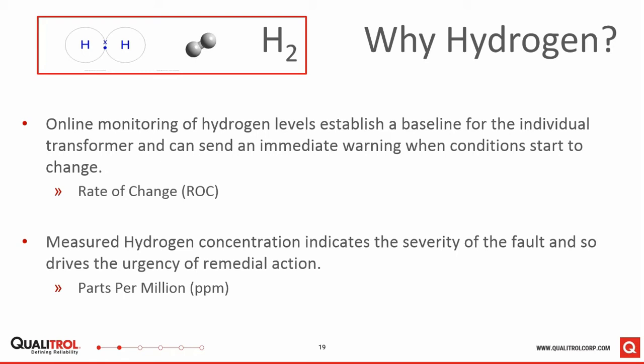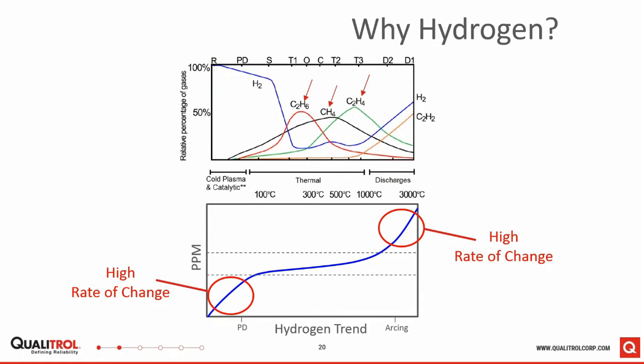Looking at the concentration itself, the ppm concentration provides some quantification of the severity of the fault, for the simple reason that the more gas present is likely to equal a more significant fault. So concentration equates to seriousness of the fault, and rate of change equates to the trend. But it's important to note that both values are related to both conditions, and they're never considered in isolation. Both are important, and it's for this reason that there's significant value to online monitoring. It gives you a day-to-day picture of the condition based on these two important parameters. This is a slide that Leon has put together, and he's going to talk you through the subtleties of what we can see here.